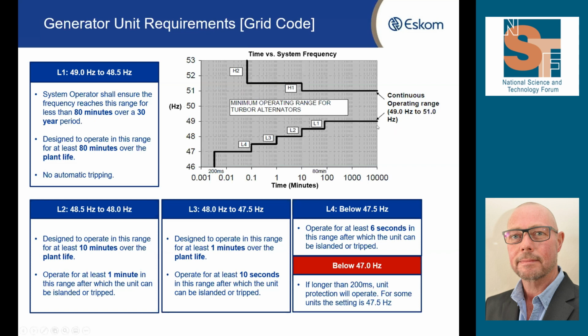And you can see that for the most part, as long as we're keeping the frequency between 49.0 hertz and 51.0 hertz, we expect the generators to be able to operate continuously within that range. As we move towards the left-hand side, I'm going to concentrate on the lower frequency band, but we have similar problems in the higher frequency band.